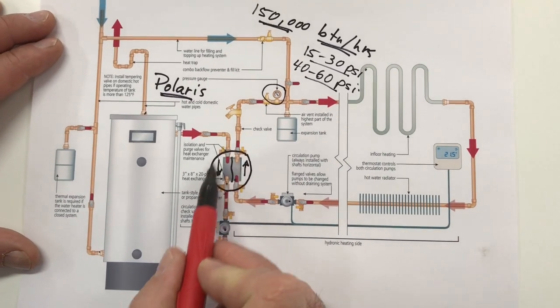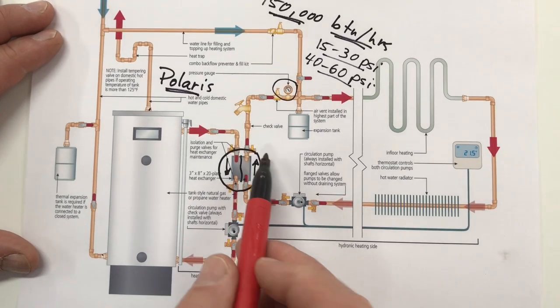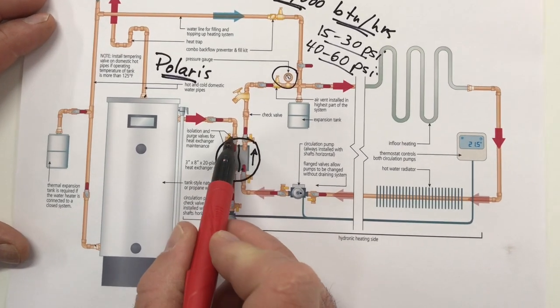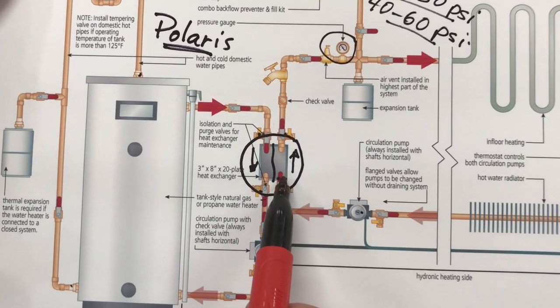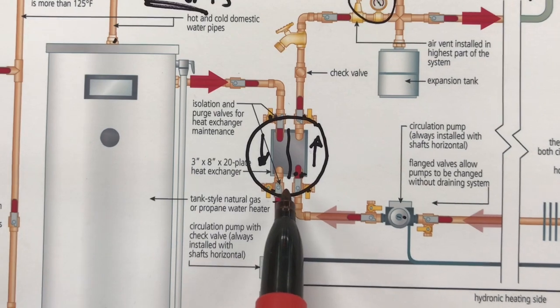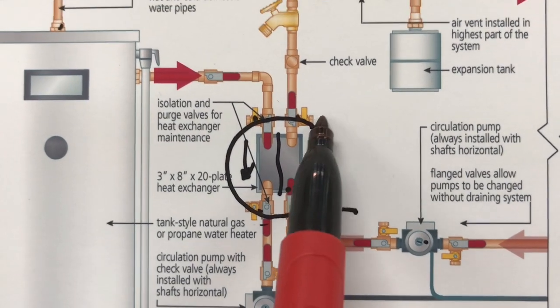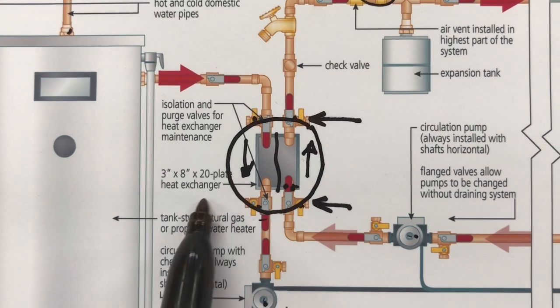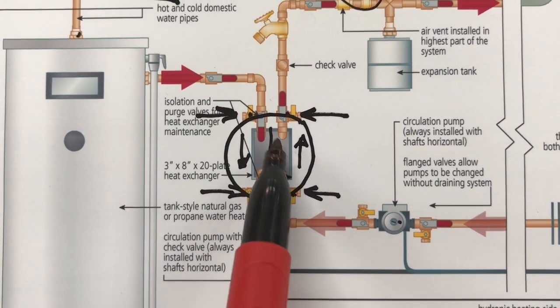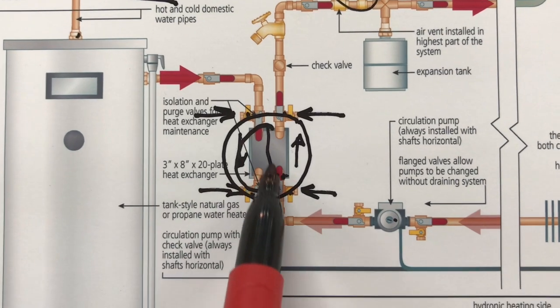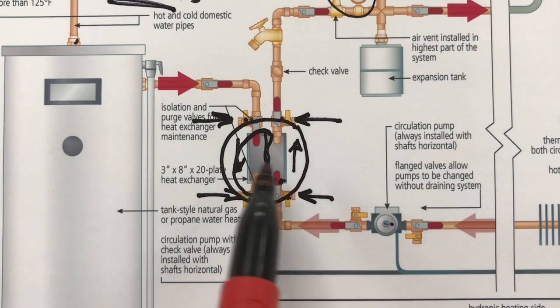Now if you do have a separate heat exchanger like this you are going to have to do the vinegar treatment and that's why I've installed these flush valves here. You can shut off the isolation valve, open up these ports here, and you can flush some vinegar through there with a pump. Usually that only has to happen on the domestic side of the system not the hydronic side which doesn't build up minerals the same way.